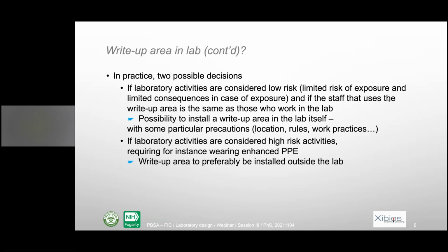And if it's the same staff that uses the write-up area as those who work in the lab, in that case, it's possible to install a write-up area in the lab itself. It might also be more convenient, and so it could be a good thing. We should take some particular precautions with respect to location, rules, and so on, and we'll come back to that immediately. The other possible decision is if you consider that the laboratory activities are high-risk activities, where, for instance, you would need more PPE than the basic lab coat and gloves. In that case, clearly, the write-up area should preferably be installed outside of the lab.